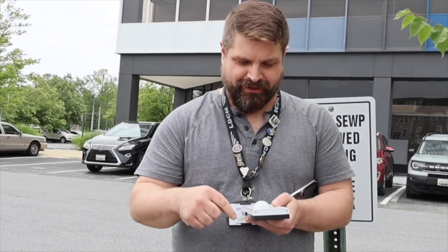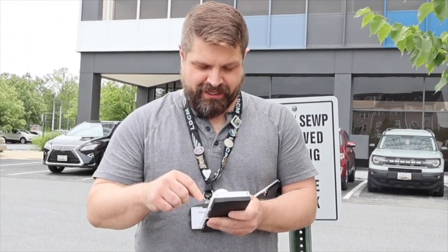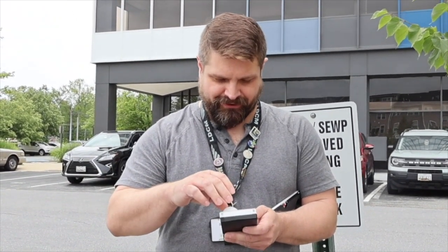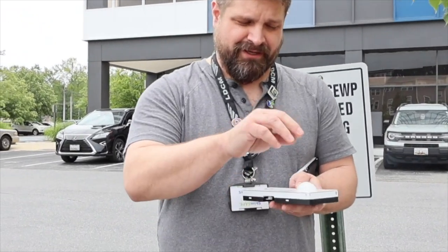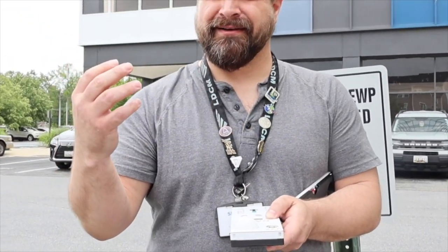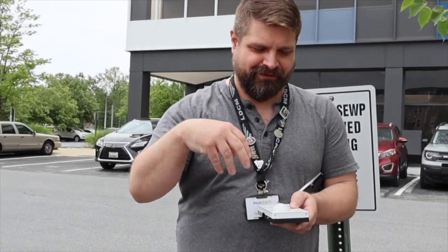And so this little ball here, which is where everyone's focal point goes to, and they always want to push it, so you might actually see a little bit of smudging on here, is a diffuser. And what it does is sort of just evens out the light. Okay, and so it's got a spectrometer sensor under here where it's measuring the amount of light in the different spectra. And this is only 10 bands from 415 to 680. Okay, and so you do point this at the sun. So how much incoming solar radiation and all that.